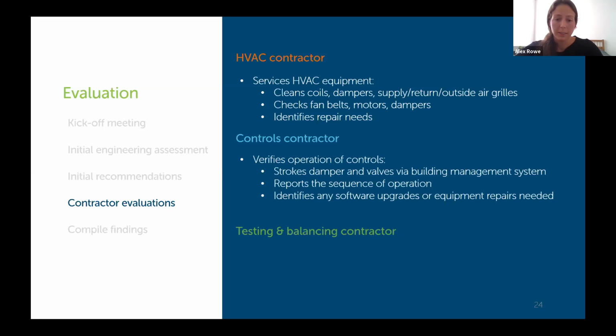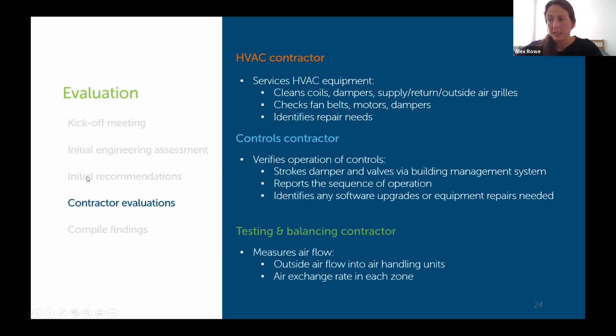Then the controls contractor verified the operation of the controls for the HVAC system. So that included stroking dampers and valves, using the building management system to see if the right airflow and heating and cooling is actually happening as intended. Then they also reported out what the sequence of operation actually is in the building management system relative to what it was designed to be, and then identified any software upgrades or equipment repairs that were needed. The testing and balancing contractor then came in and measured both outside airflow into the air handling units and then supply and return airflow into each zone to then calculate the air exchange rate.